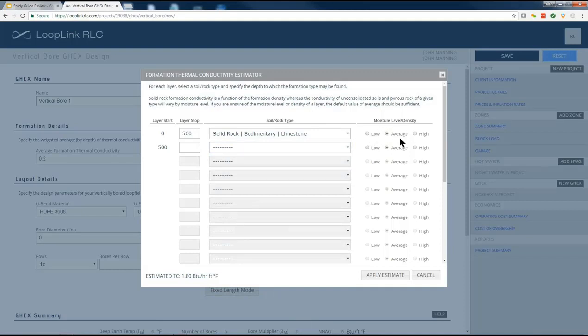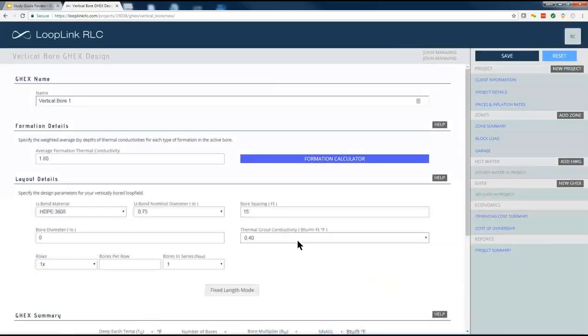We tried to keep this fairly simple, but generally speaking, I recommend leaving those values at average unless you've got better information and you know that the water table is fairly low or fairly high in an area. You can adjust that up or down as needed. I'm just going to leave that at the default value and hit apply. And as soon as I did, notice limestone is pretty conductive in terms of heat transfer. But I'll go ahead and use that 1.8 formation thermal conductivity value.